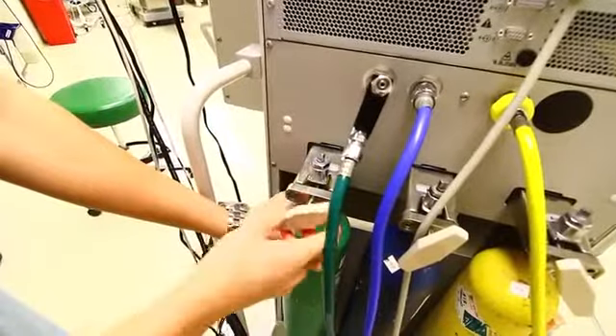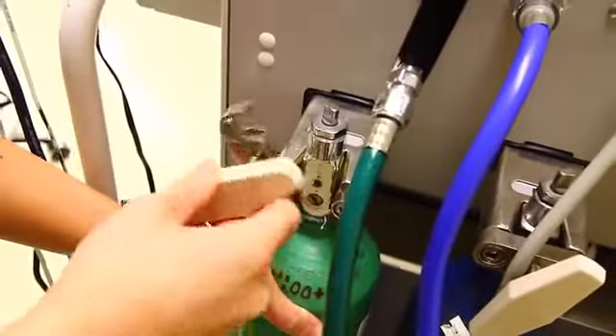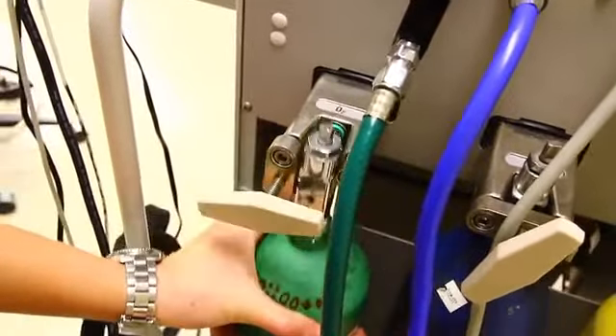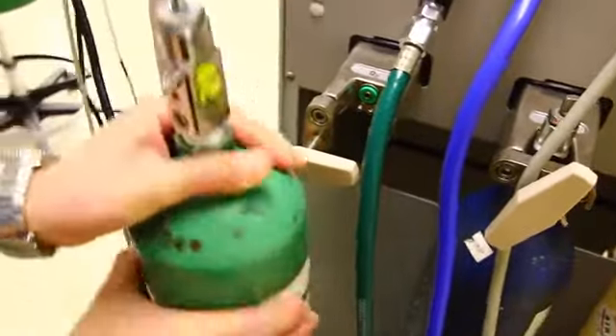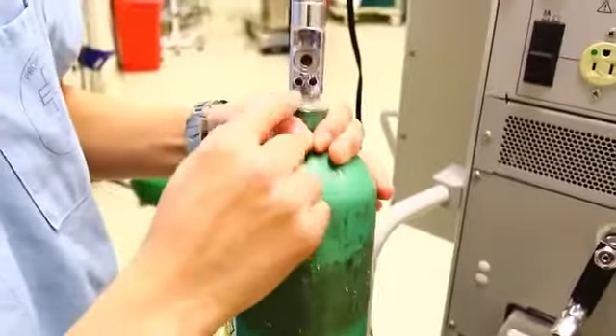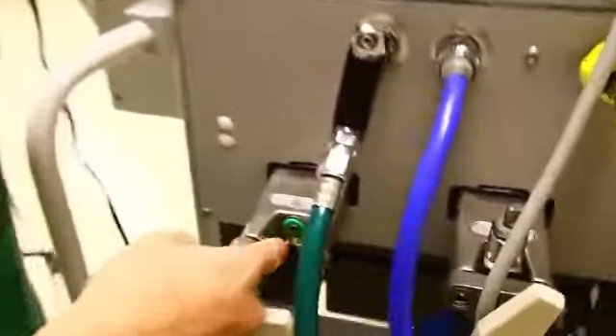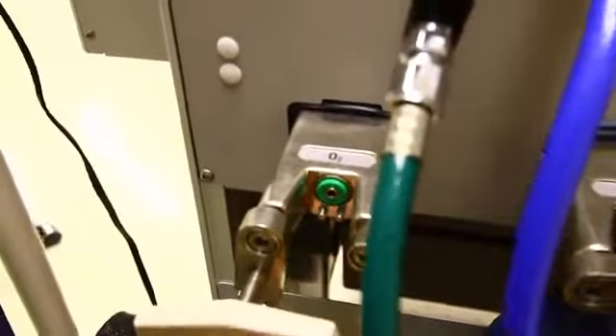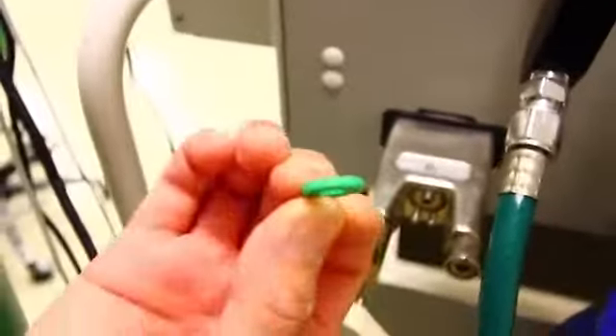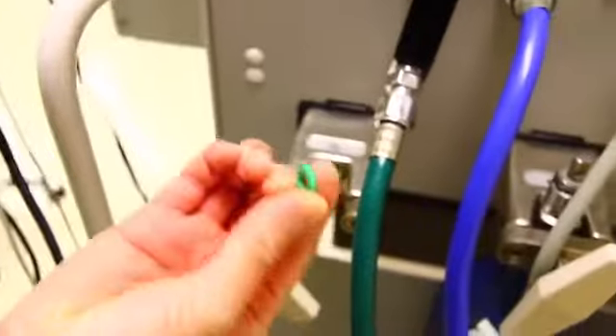To remove the oxygen tank, turn the handle counterclockwise. Remove the tank. Notice the pin index safety system. Check the O-ring for integrity and replace it.